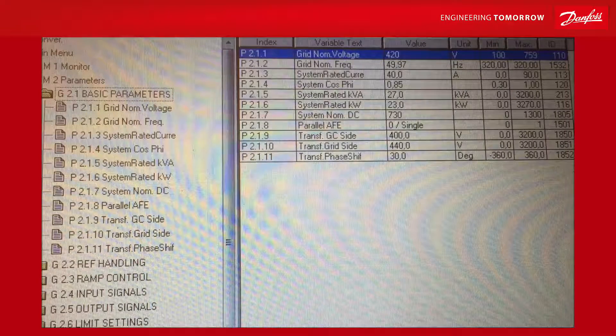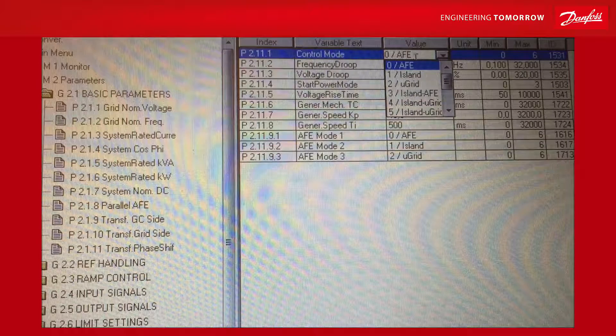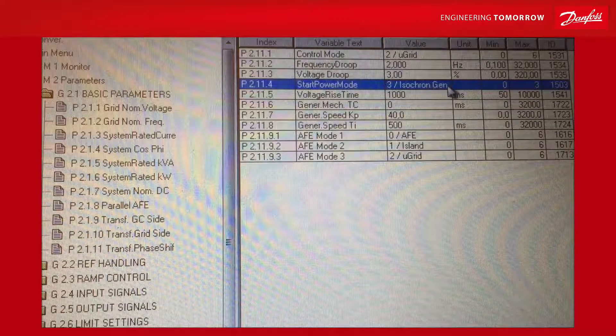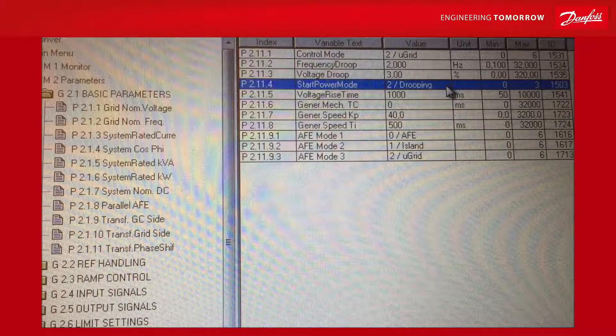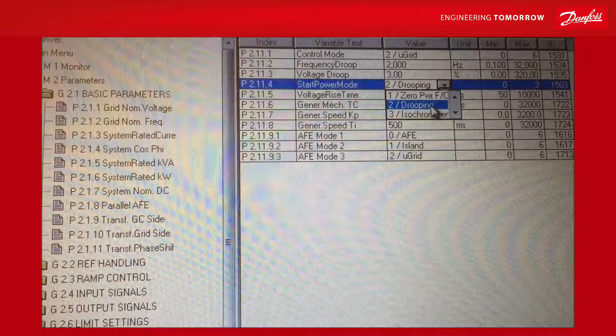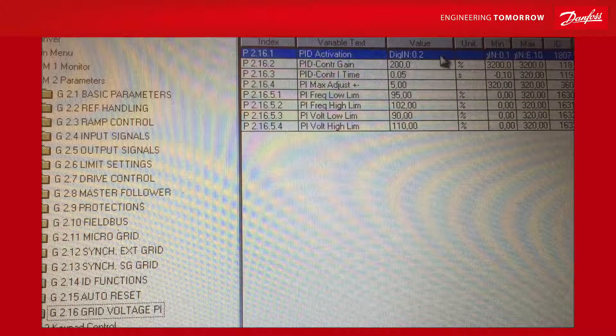We have to take a look at the microgrid mode. We change it from Active Front End (AFE) to Ugrid mode. Here we can see it is set to start power mode isochronous, but since we are not connected to a grid yet, we change it to drooping. You can select between several modes, but basically we are using drooping and isochronous. In the chapter for grid voltage PI regulator, I check that it is turned off — it is off at 0.1 and on at 0.2. For commissioning without a grid I want it off, otherwise it will affect my voltage and cause confusion.